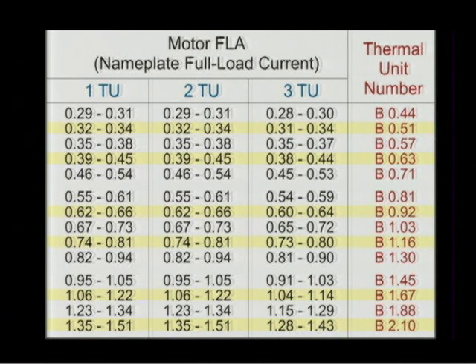And Dan, you had that little tiny device. Any of those have a number on them? Any kind of B number, anything identified in some way? What does that one say? The GE ones are actually pretty good because the part number is actually the amperage. C955A means that this one's good for 9.55 amps.